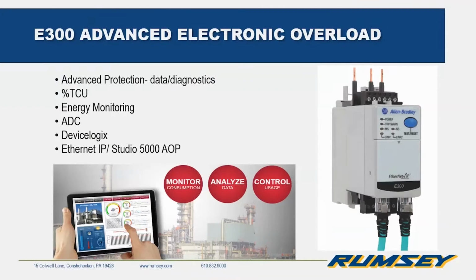So what makes this powerful is because this is a networked overload, we can get that data, pull it out, and display it. So with that percent TCU, we now know exactly when this overload is going to trip, and we can get it down to the second. As soon as it hits 100% TCU, we know it's going to trip. So we can set up alerts at 90%, at 95%, to alert maintenance or to alert the operator, let them know that we're coming up to an issue and it needs to be dealt with. So this could be the difference between keeping the line running or having unplanned downtime. So this is a powerful feature.